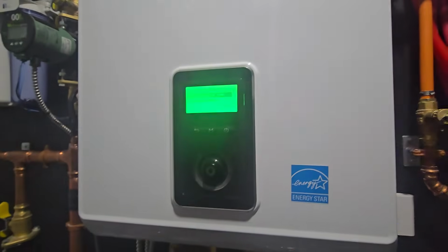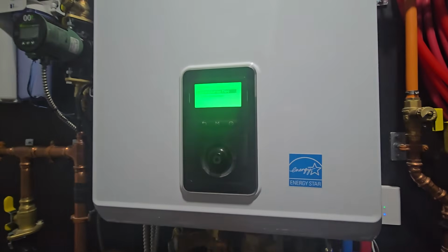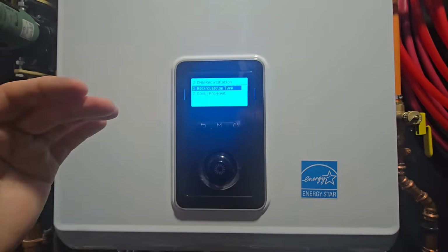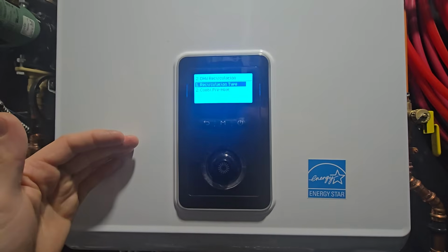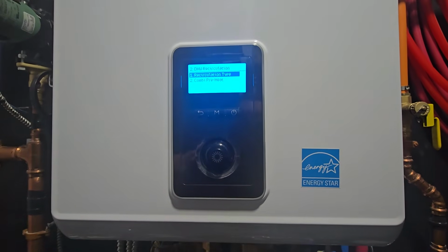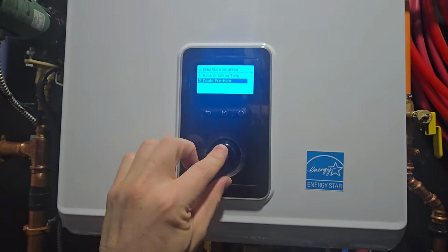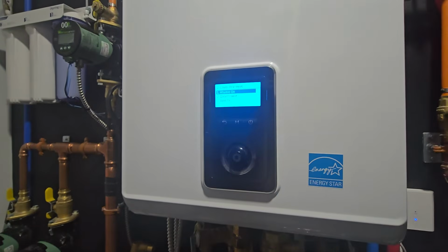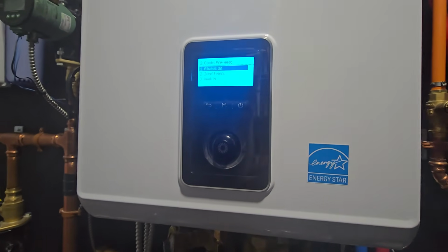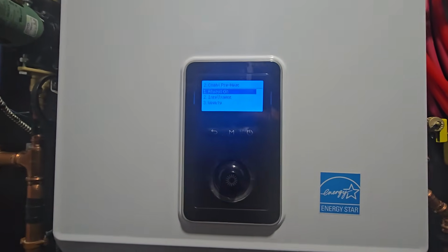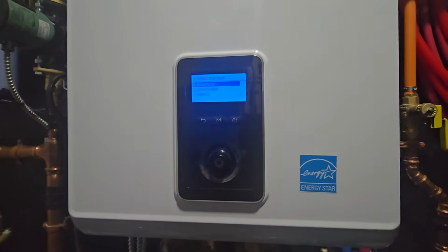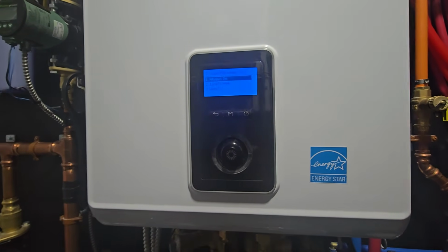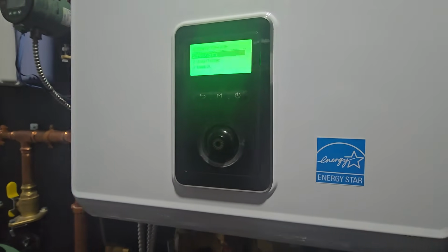Now what that's going to do is just always monitor the temperature of the domestic hot water within the heat exchanger, and it'll keep that water set at 130 degrees in there, which really just gives you a little bit of a boost when you do have a call for hot water. So essentially what's happening is the boiler is just going to kick on its own by monitoring what temperature that water is inside there, so that when you turn on your faucet, instead of waiting maybe 10 seconds, 15 seconds, maybe you only have to wait 5 or 10 seconds. It just all depends on the length of tubing you have to your faucet.